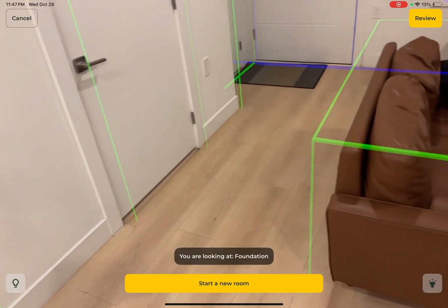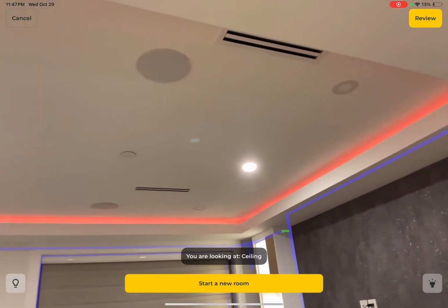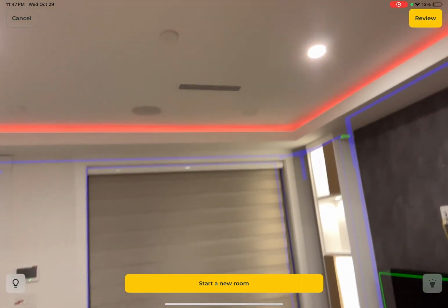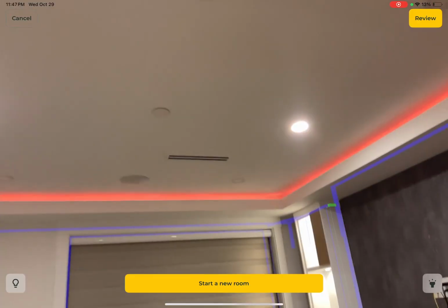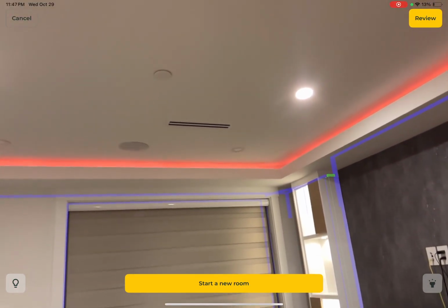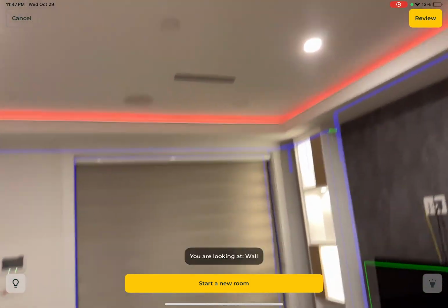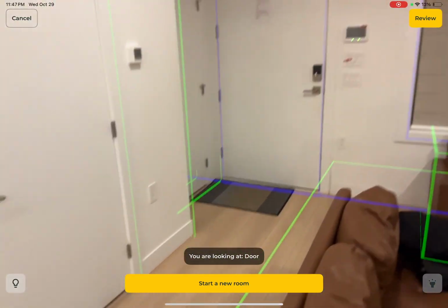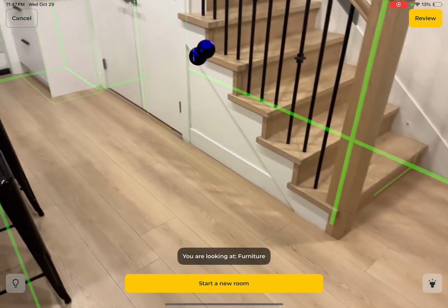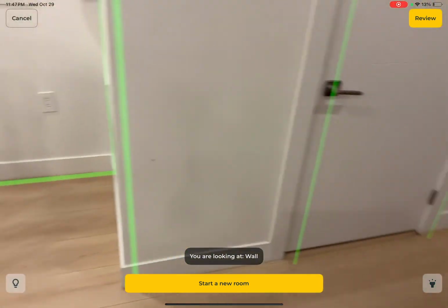Another thing to note is at the top, I see these air supply grills. These air supply grills, because they are moving through heated space, I know my upper floor is heated. I don't have to really do any changes here, but if it wasn't, then I would have marked at least one of them for the F280 standard. Okay, so that's as much as I need to do for this room. Let's go to the bathroom in the next video.